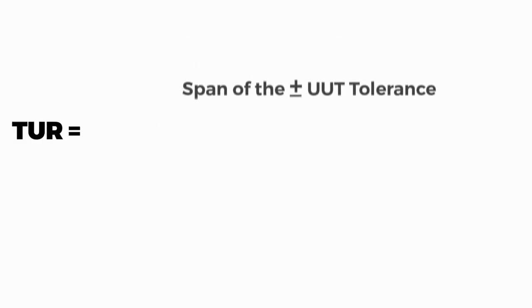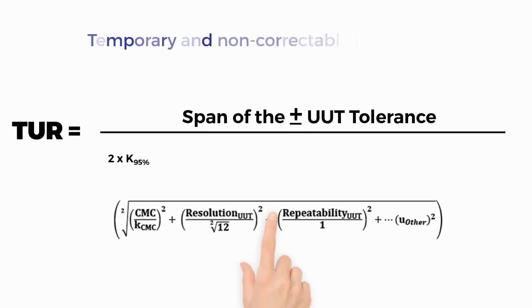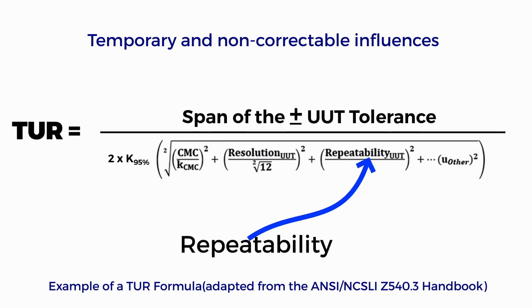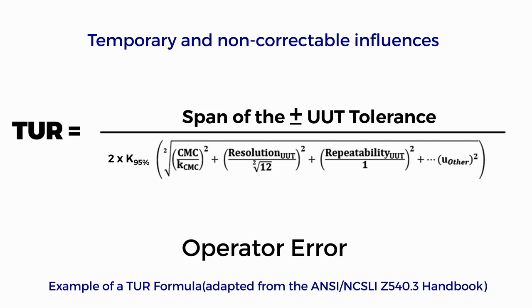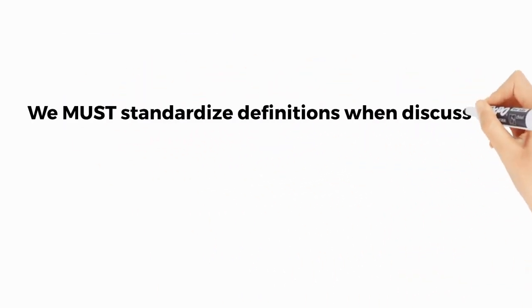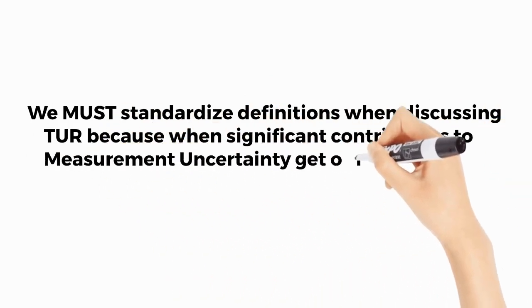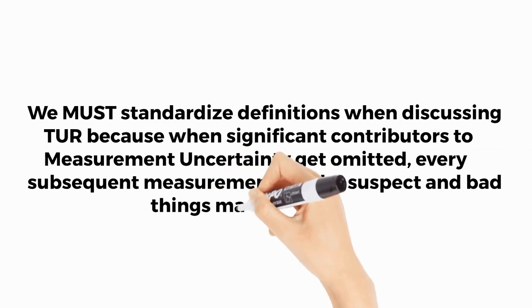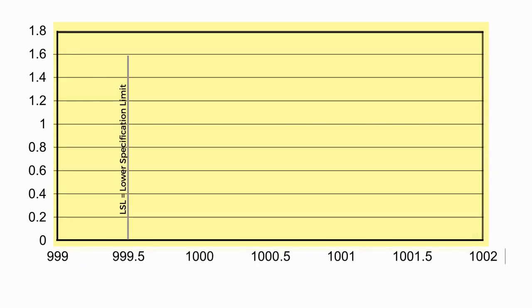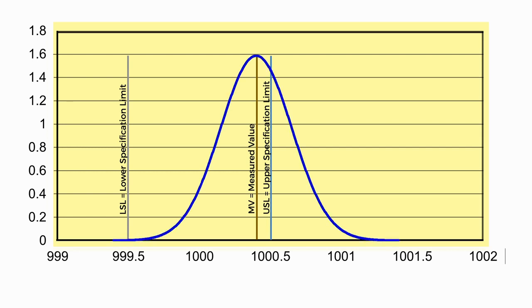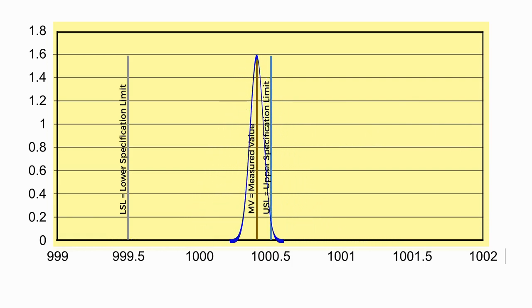The formula for TUR consists of the span of the tolerance in the numerator. The denominator includes temporary and non-correctable influences incurred during the calibration, such as repeatability, resolution, error in the measurement source, operator error, error in correction factors, environmental influences, and others. We must standardize definitions when discussing TUR because when significant contributors to measurement uncertainty get omitted, every subsequent measurement will be suspect and bad things may happen. When we use the appropriate formula and draw the concept, we draw the lower and upper specification limits at 999.5 and 1000.5. Next, we put in the location of the measurement at 1000.4. The calculated calibration process uncertainty determines the width of the distribution. As you can see, the larger the measurement uncertainty, the larger the risk relating to the measurement location. The smaller the uncertainty, the lower the risk.